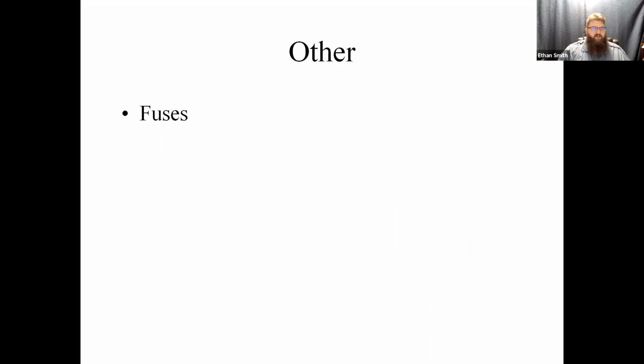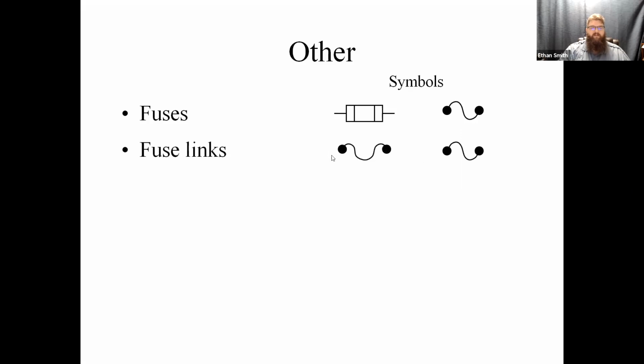We talked a little bit about fuses already. So fuses simply have an element in them that melts at a set value of current. There's lots of different symbols for them. These are the 2 most common ones that you'll see, either a box with 2 lines in it or the fusible link type symbol right there. Okay. Fusible links are single use fuses, typically used as rollout switches in older furnaces. Last chance high limits, things like that are listed as fusible links.